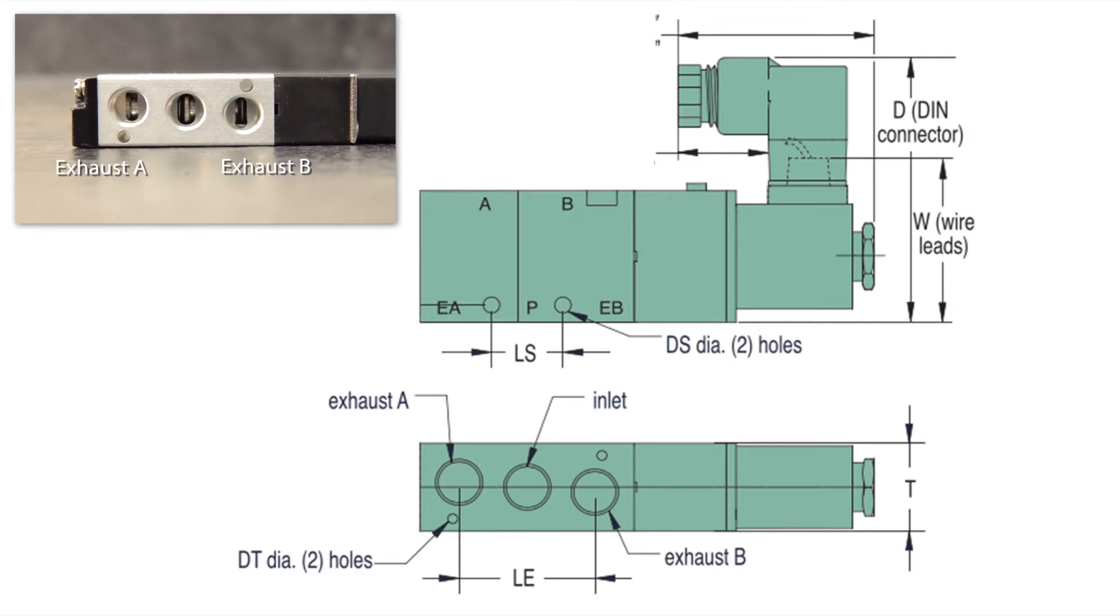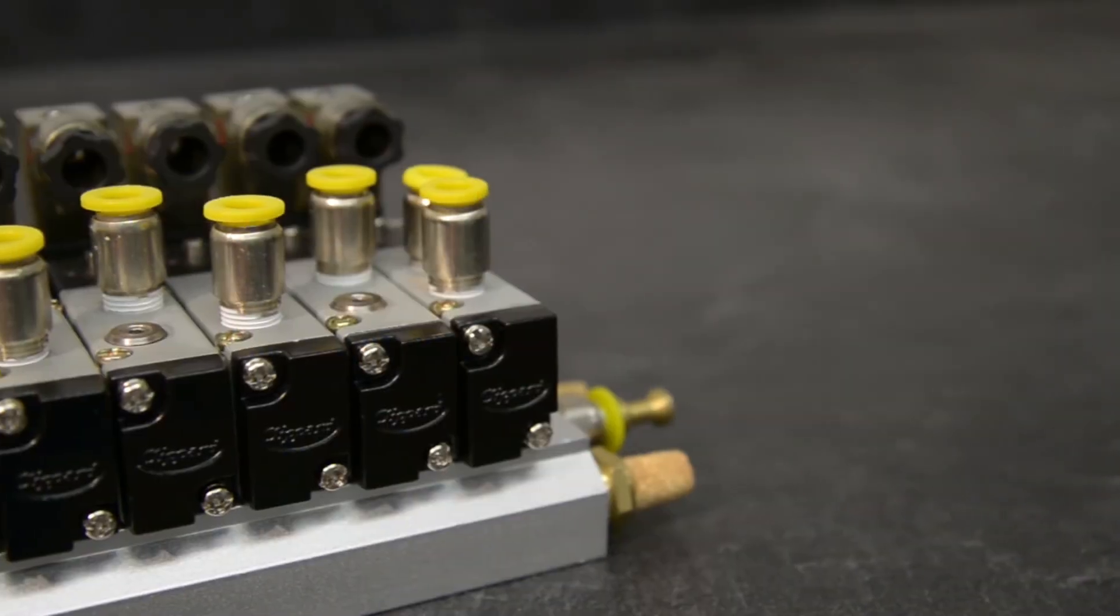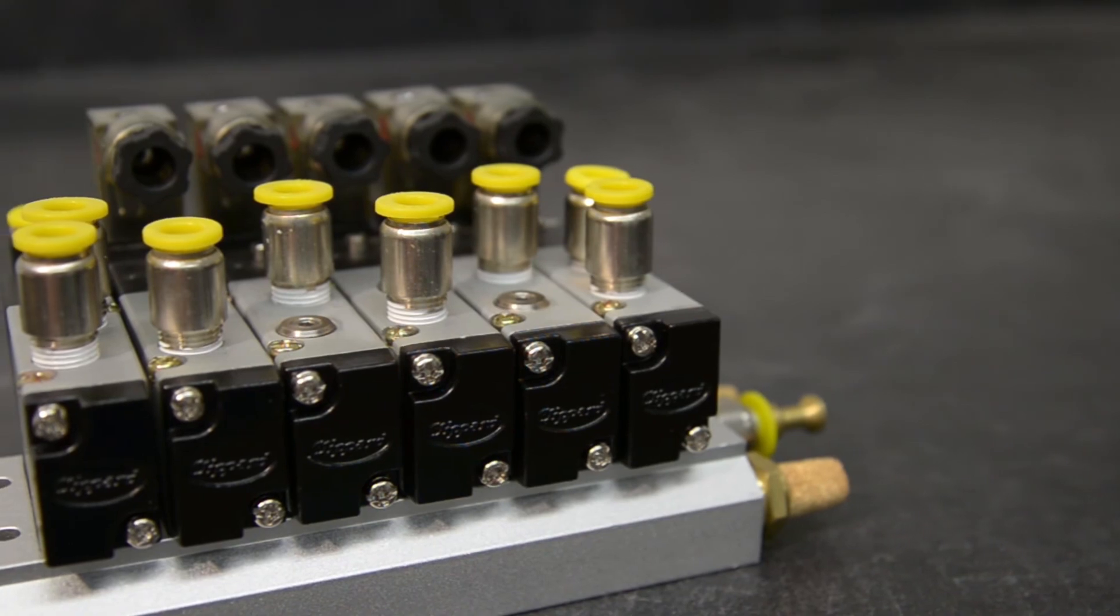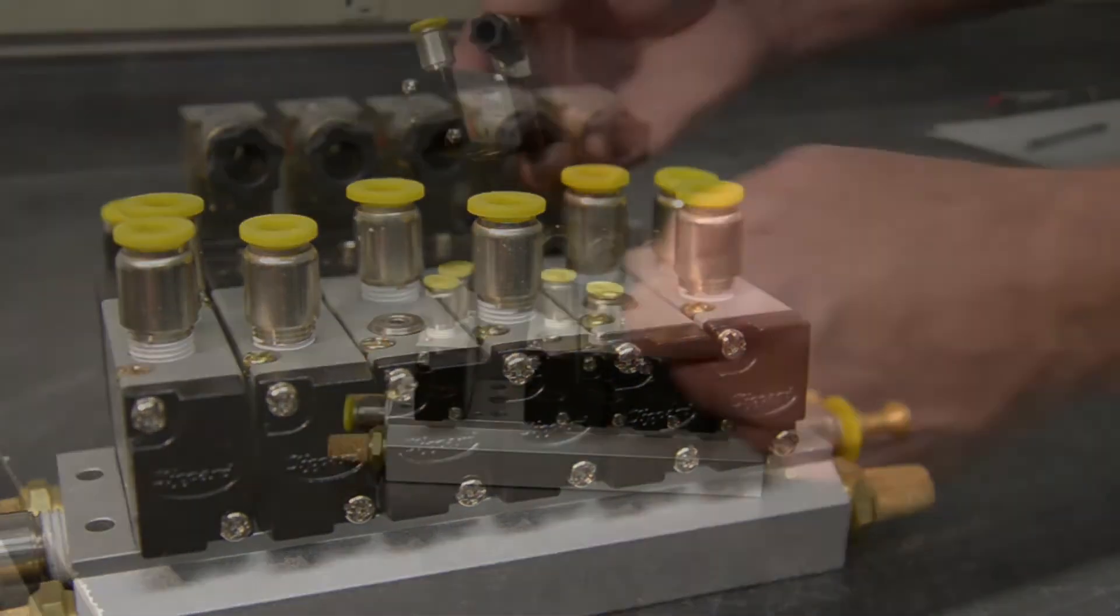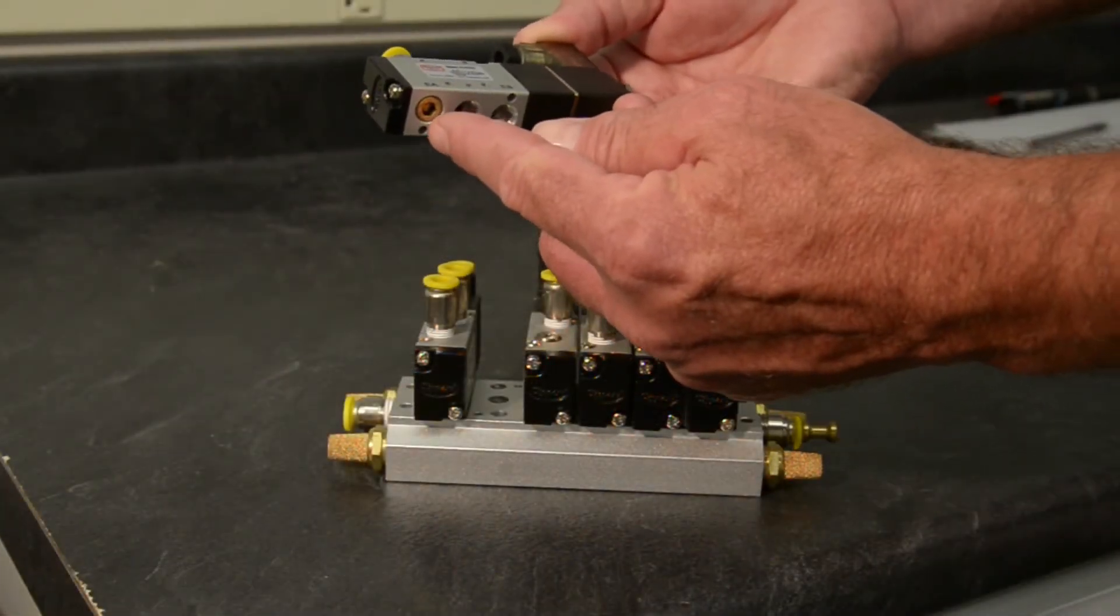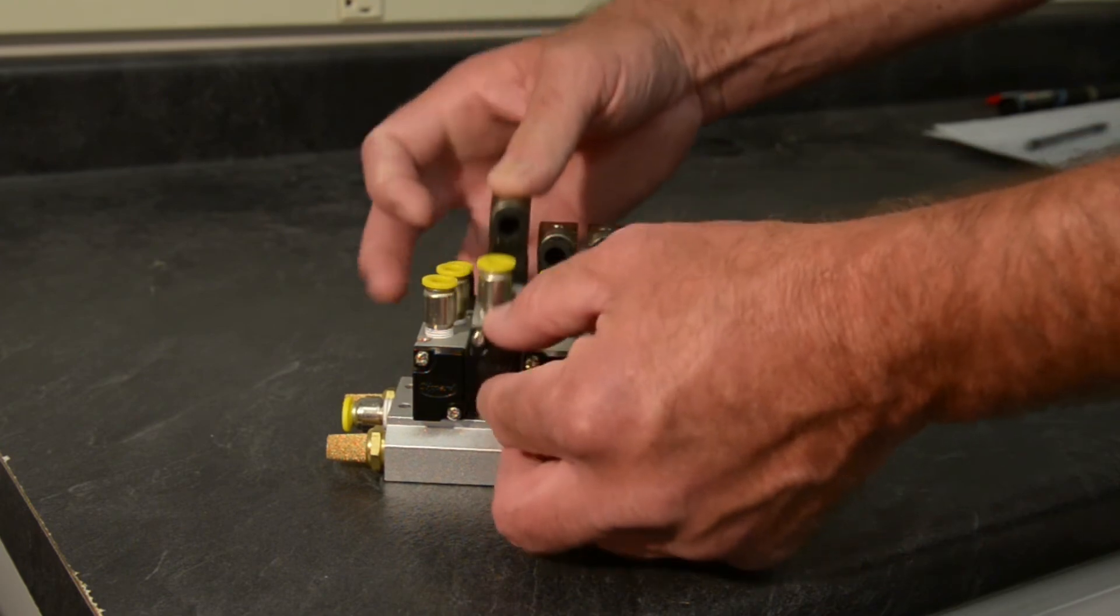When the valves are mounted on a common manifold, the supply port P is between both exhaust ports, while your A and B outputs are located on the top of the valve. It is important to remember that we are going to mount the valves on a manifold. It is essential to use flush plugs on the exhaust ports which will be facing the manifold in order to get a good seal.